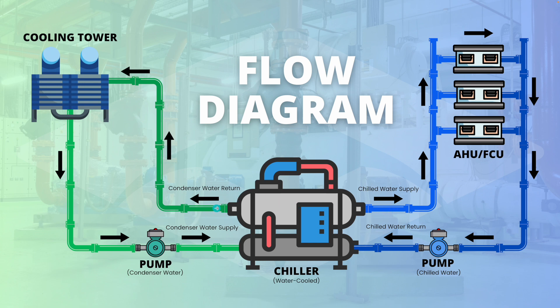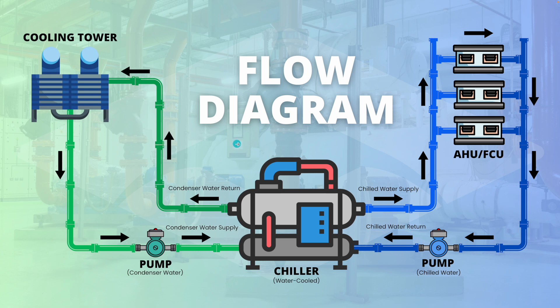On the condenser water side, the chiller performs its refrigeration process to transfer heat from the chilled water to the condenser water. The condenser water is heated up and leaves the chiller at about 35 degrees Celsius. It then goes to the cooling tower, which sprays it down and brings in ambient air to cool it. The cooled condenser water returns to the chiller at about 30 degrees Celsius — another 5-degree temperature difference. This is how the four components work and how the chilled water system basically operates.